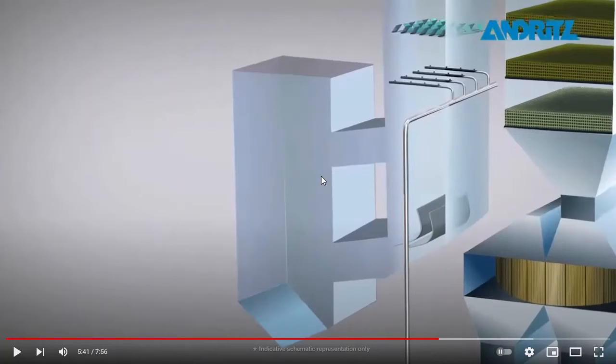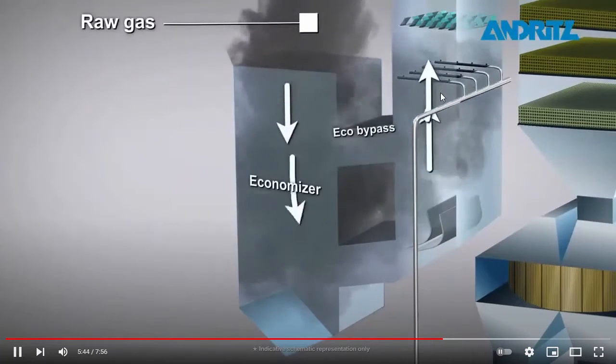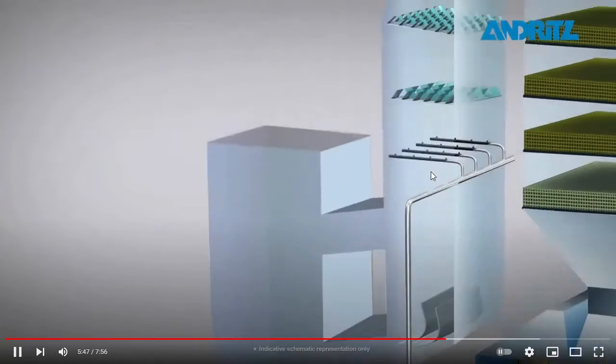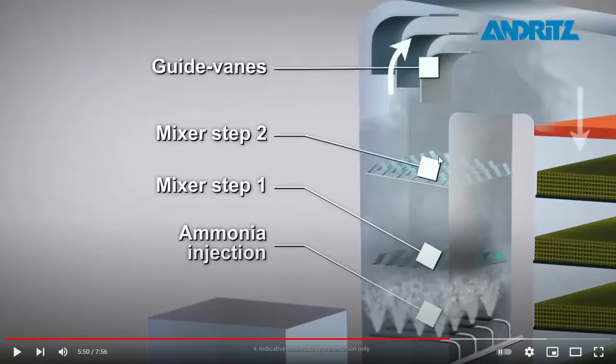All right, so then this is the pollution control equipment, right? So we said we have all that hot gas that's coming out the back. So you've got the gas with nitrous oxide in it, sulfur in it, and then fly ash. So the first thing that we talked about was this SCR. So that's selective catalytic reduction. And so that is coming out through here. It comes up. So that gas has it sprayed in, right? It's ammonia. So it sprays that ammonia in there into the gas, and then it comes over the top.